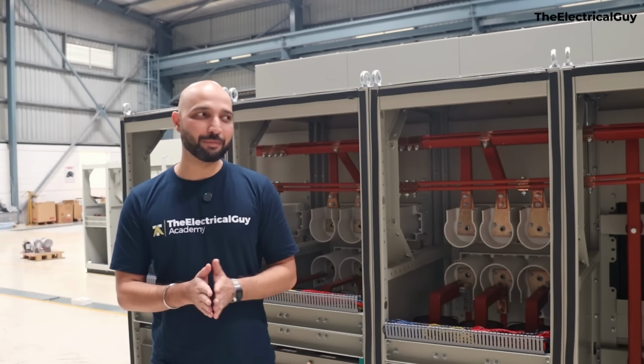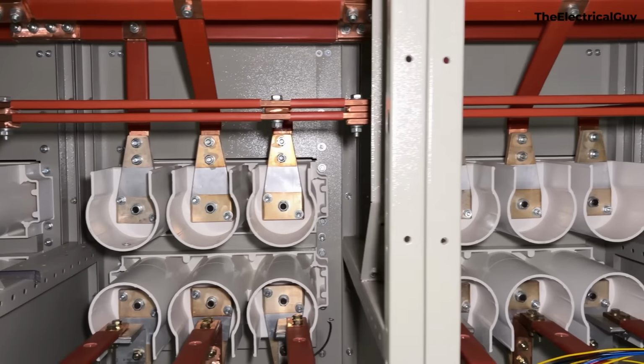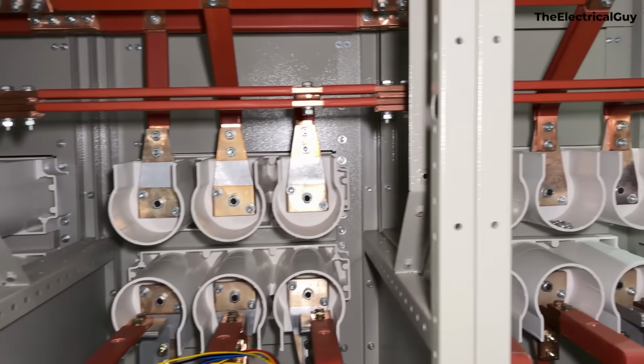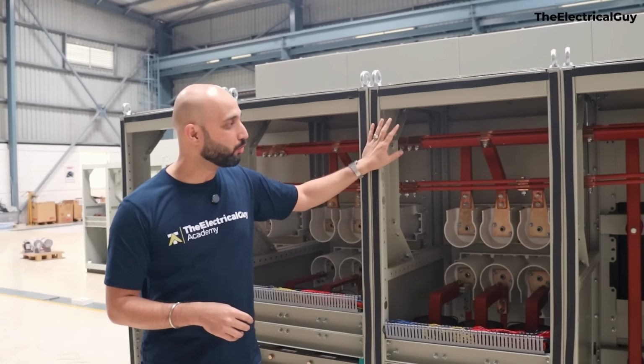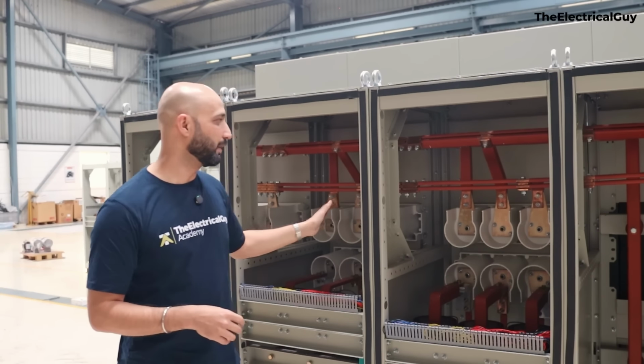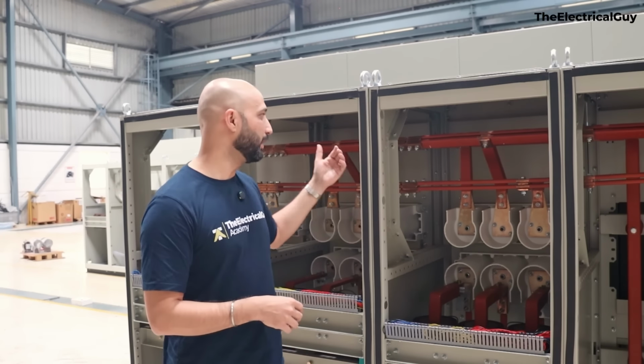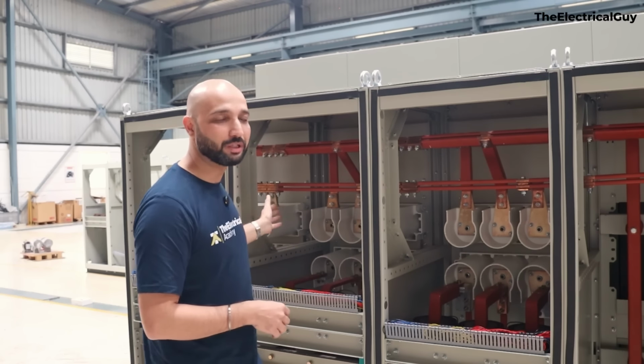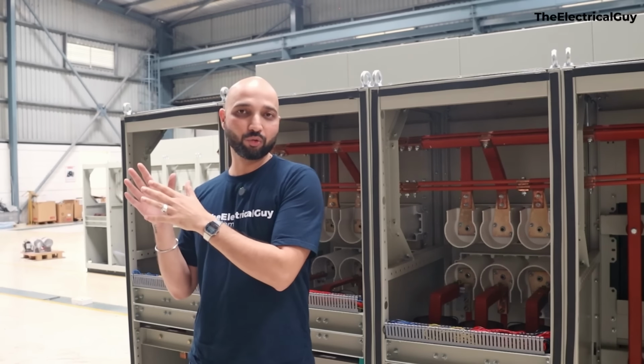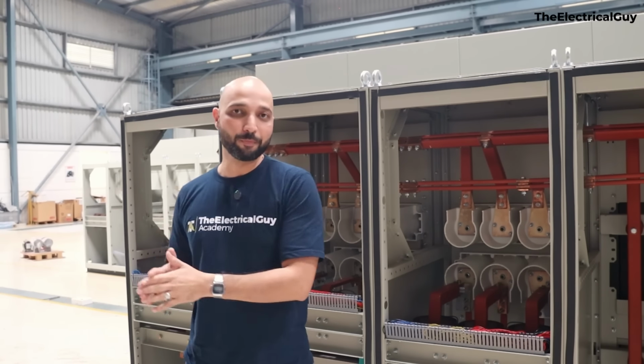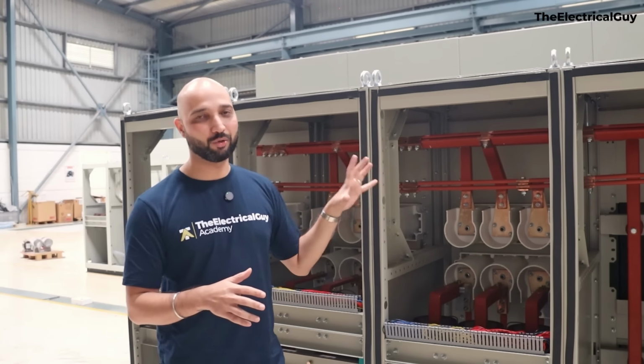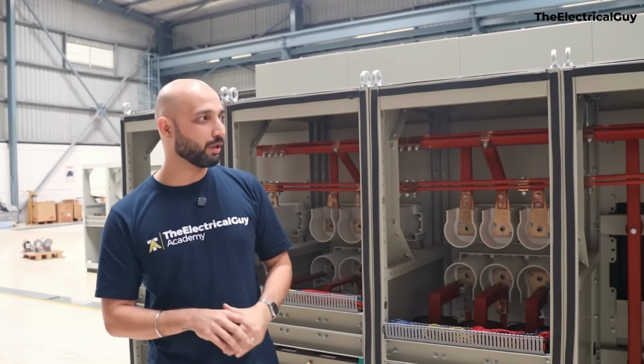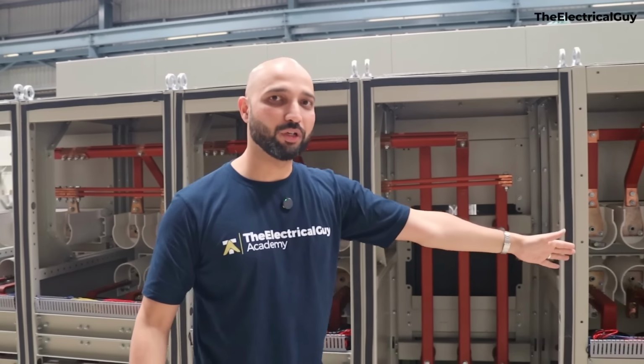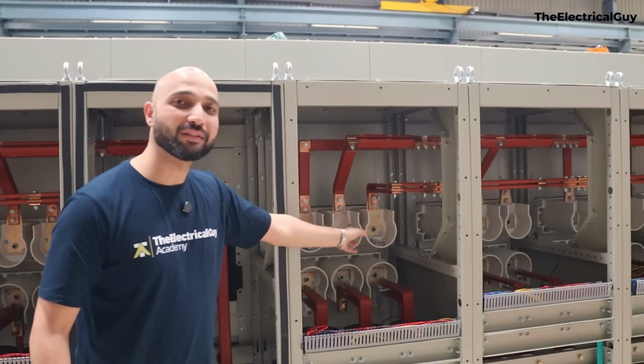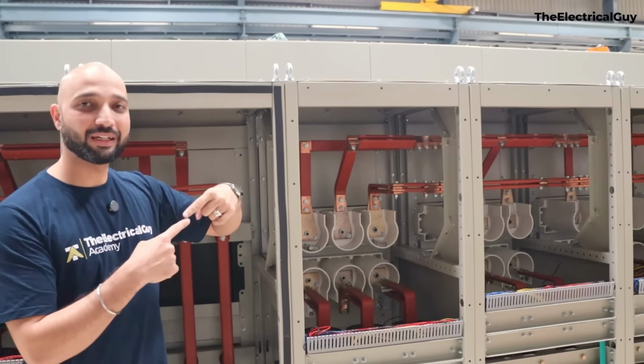All right, so now we are at the back side of our panels, and you can see the bus bars are clearly visible. So this was our incomer 2 panel, which I explained to you. You can see the bus bars that are connected here. And from this bus bar, we are feeding outgoing 3 and 4. Similarly, we also have incomer 1, which is feeding the supply to outgoing 1 and 2. But these two things are not connected together. And to connect them, what we are doing is adding a series connection, which you can see right here, using a circuit breaker. Now it's a switch inside the series connection.